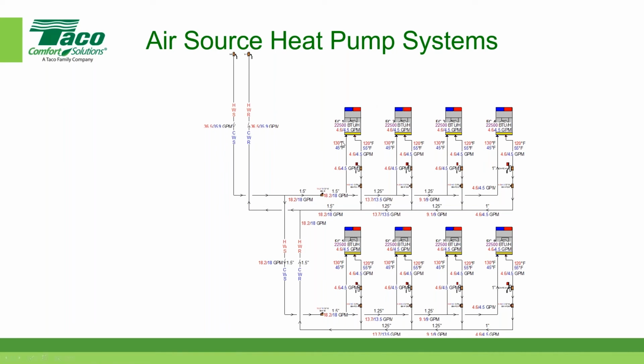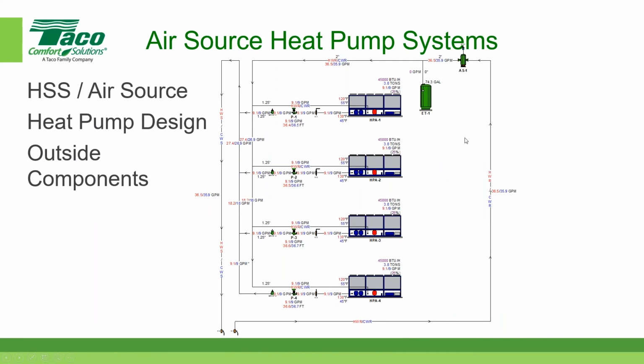So in this case, 130, delta T is 10. That's the main difference for terminal units on an air to water heat pump as compared to a fossil fuel boiler, which could have an entering water temperature of 160, return water temperature of 130. That's with a 30-degree delta T. So these are low water temperatures and narrow delta Ts. And that's how the system is configured.